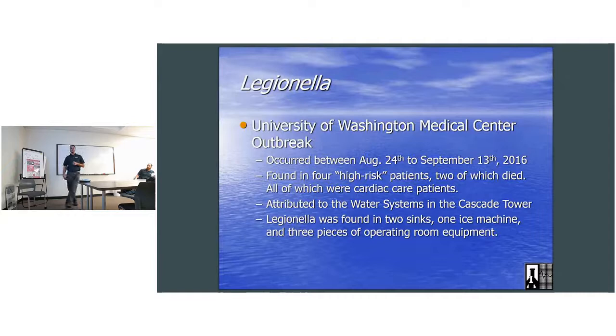And well, water management plans too that they come up with. Part of what they're going to want to know is how close is your tower to the intake to the building. If your tower is right here and your intake is right there, that's bad. That's poor design. They would want to know that ahead of time. But if it's 5 stories down and in the alleyway, or the air intake on the building is away from the tower, that eliminates one of the possibilities. Well, maybe then our Legionella is not coming from the tower, it's coming from potable water.